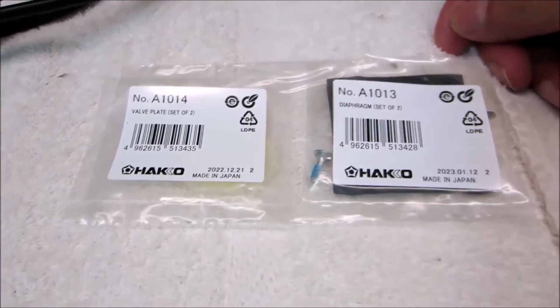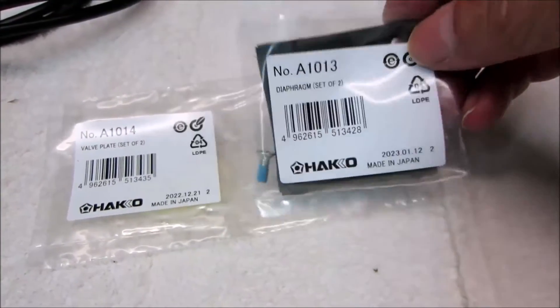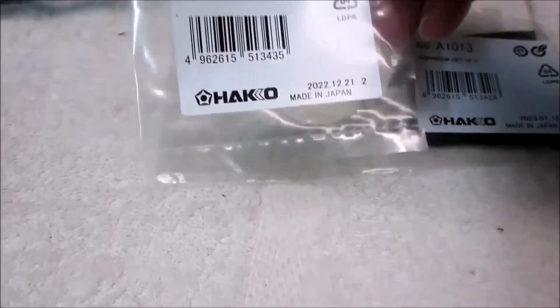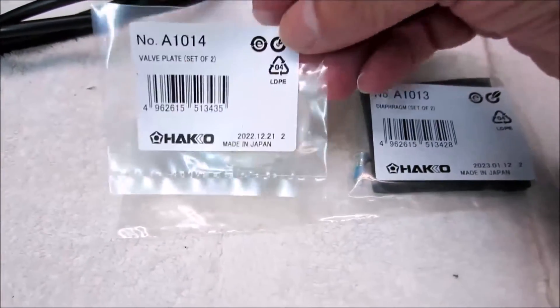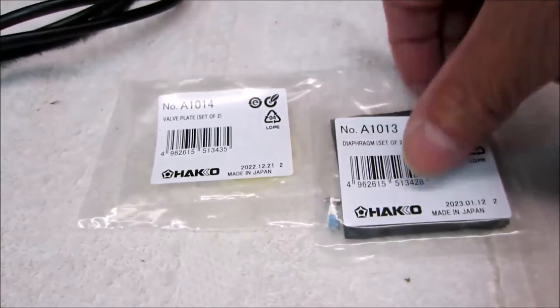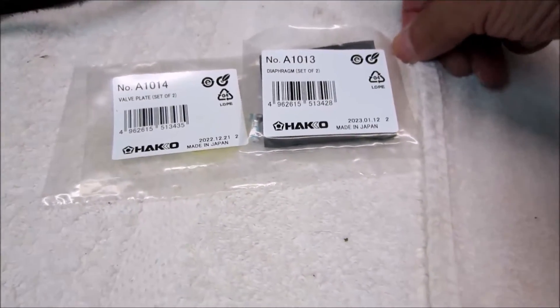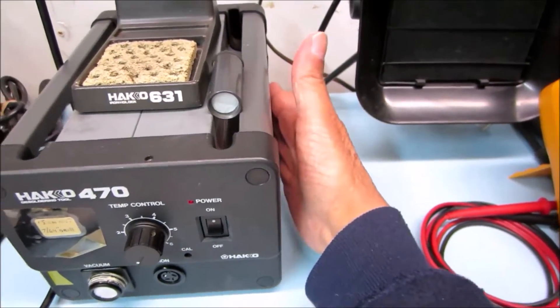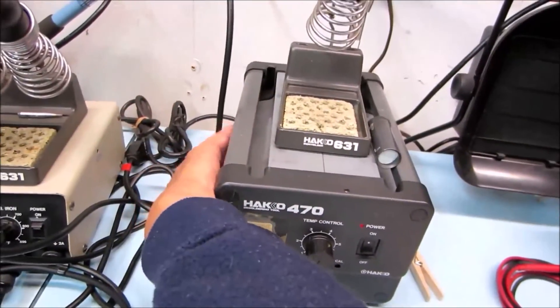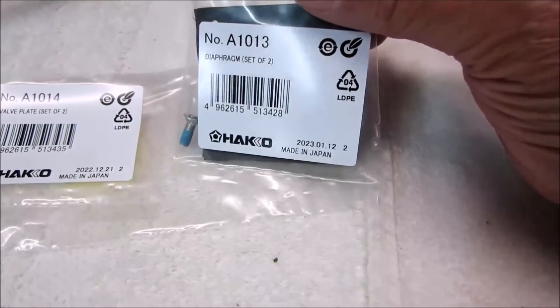So the next two suspects, lots of discussion about this online, is this diaphragm set, part number A1013, and also this valve plate set, part number A1014. Now, this represents about $45 with shipping for these two parts total. That's what I paid. I bought some new ones. And these go on either side of the pump. The pump motor is in the middle of this box. So you've got one set on this side, one set on that side of the motor. They're very easily installed. Here's my old ones.